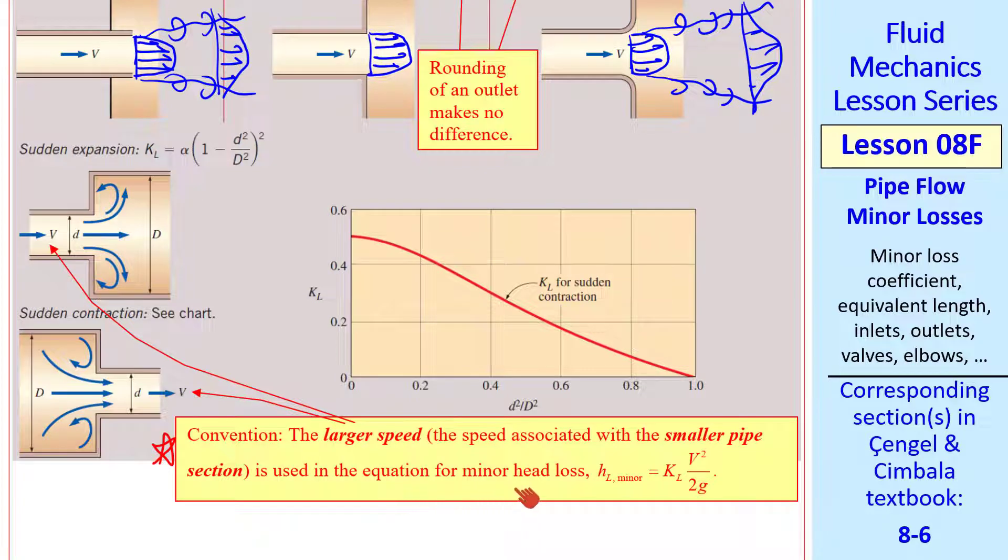Note that by convention, the larger speed, that associated with the smaller pipe section, is used in the equation for minor head loss. This V is the larger V of the two. So for the expansion, we use V1. And for the contraction, we use V2.